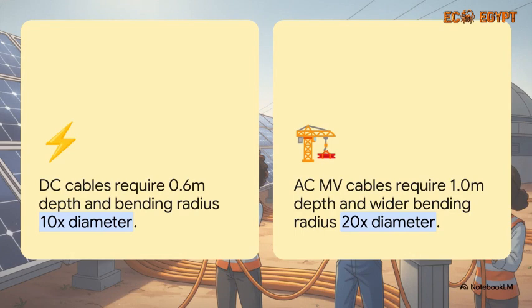So how exactly do we safely separate all these varying voltage levels underground? I mean, burying thousands of meters of cable isn't just about digging a random hole, right? Comparing the installation requirements for multiple types of cables reveals a huge safety principle. Because AC medium voltage cables carry vastly more hazardous energy than standard DC solar cables, they demand much deeper trenches, a full 1.0 meter depth minimum, plus significantly wider bending curves. This prevents insulation stress and physical crushing under the weight of passing maintenance vehicles. Meanwhile, the lower voltage DC cables only require a 0.6 meter depth.